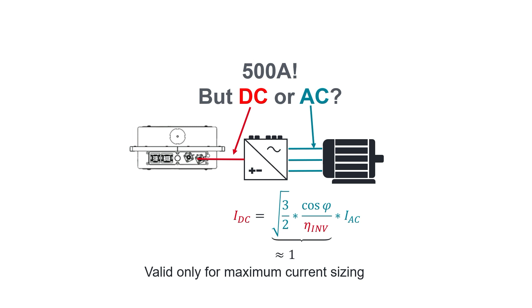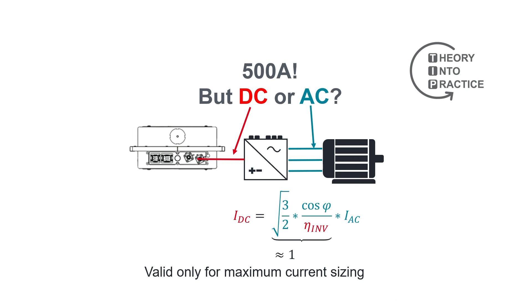So when it comes to current sizing, it's both okay to respect that 500 amps for DC and for AC. Again, that's a bit of juggling with equations, but in the end it's about theory into practice, giving us a rule of thumb for battery sizing and also drive sizing, which we want to look into more closely now.